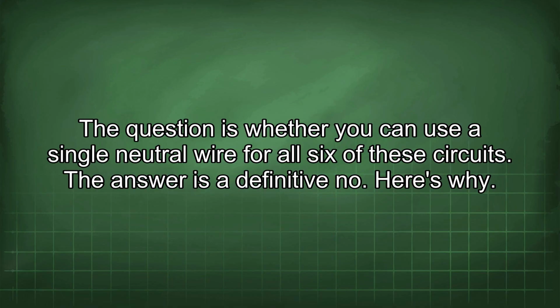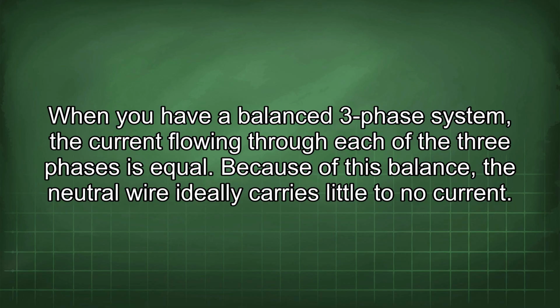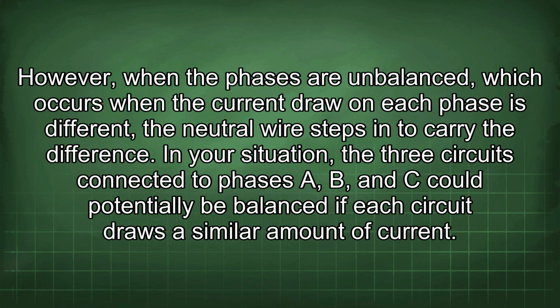Here's why. When you have a balanced 3-phase system, the current flowing through each of the 3 phases is equal. Because of this balance, the neutral wire ideally carries little to no current. However, when the phases are unbalanced, which occurs when the current draw on each phase is different, the neutral wire steps in to carry the difference.